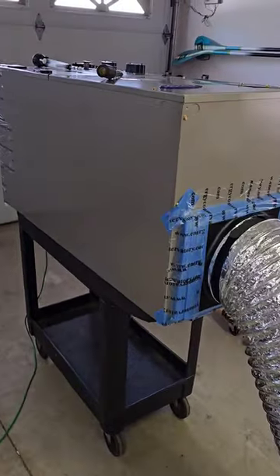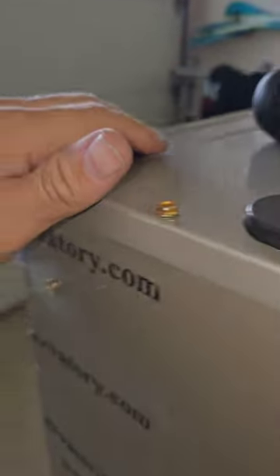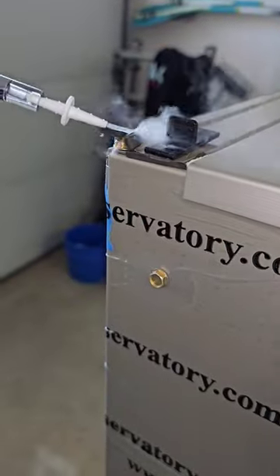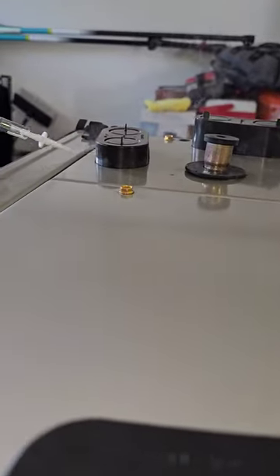Most of the leakage, before I even installed it - this thing has a lot of gaskets, so if you had a less efficient air handler, I'm sure it would have even higher leakage. But I can feel it around the filter door right here. It's going crazy around the refrigeration line connections and the drain line connections.